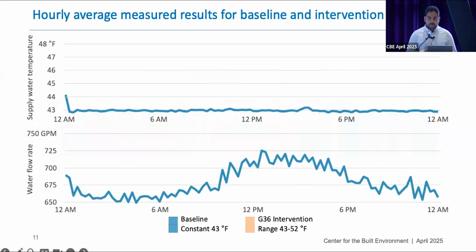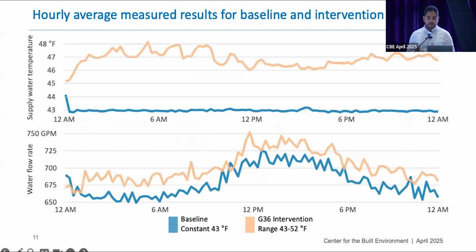So here you see 2 plots with the same x-axis, which is the hour of the 24-hour day. The top plot is chilled water temperature, and the bottom plot is the water flow rate. As expected, the baseline maintains a constant water temperature of 43 degrees Fahrenheit because that's what we define it to do. And looking at the water flow rate, it ranges from 650 gallons per minute all the way to 725 during peak condition. So let's compare to the Guideline 36 intervention.